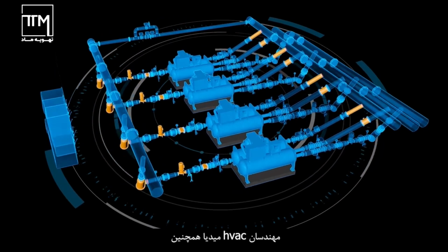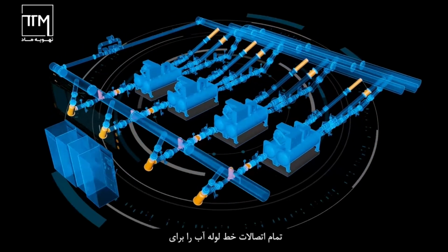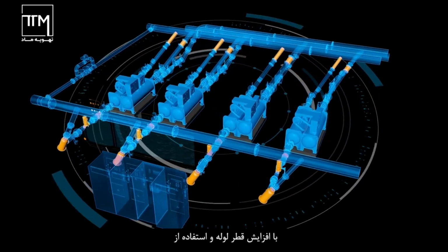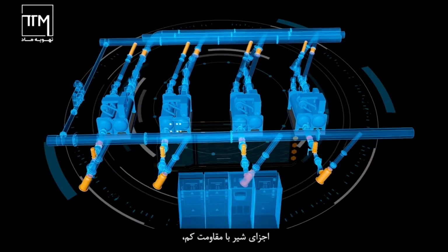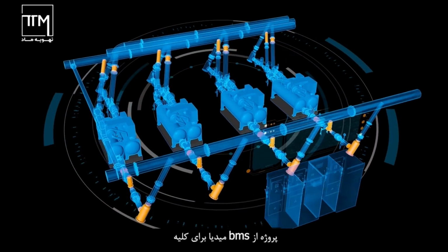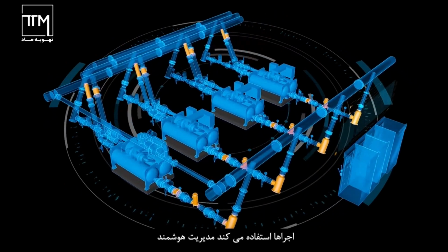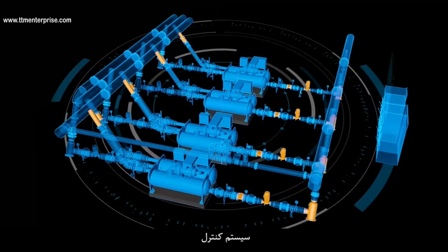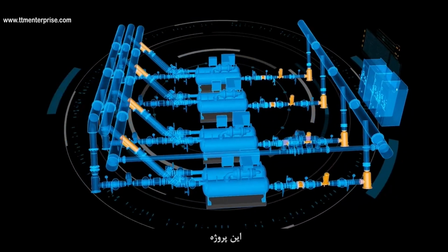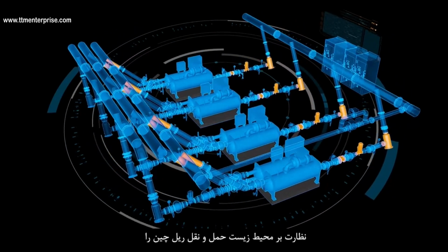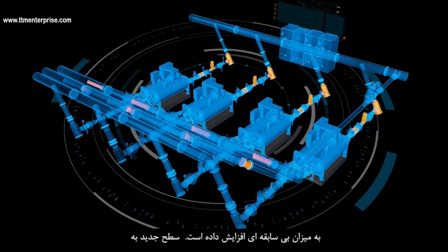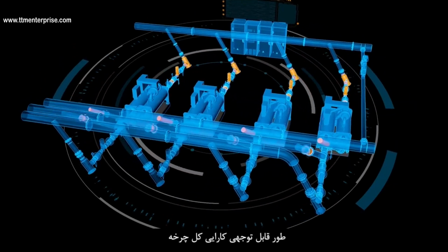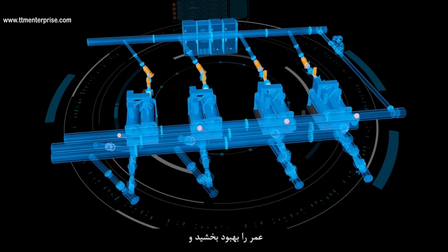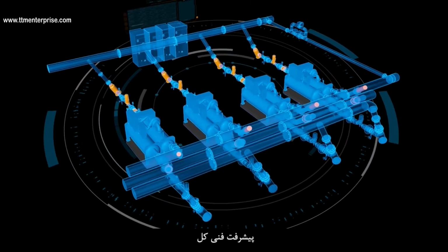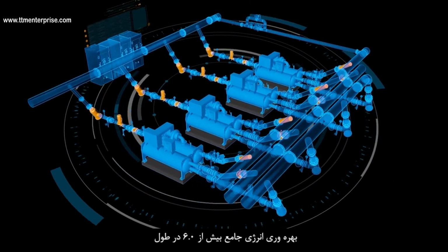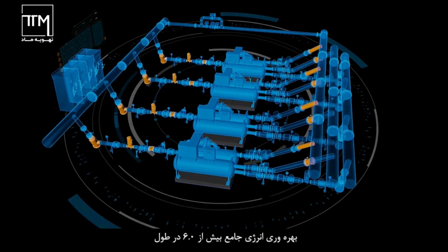Midea HVAC engineers also optimized all the water pipeline connections to reduce pipeline resistance by increasing pipe diameters and using low-resistance valve components. The project uses Midea BMS for all-round intelligent management of the chillers and the terminals, as well as the control system. This project has raised the energy efficiency level of China's rail transportation environmental monitoring system to an unprecedented new level, significantly improved the whole life cycle operation efficiency, and driven the technical progress of the whole industry, with a comprehensive energy efficiency of over 6.0 throughout the year.